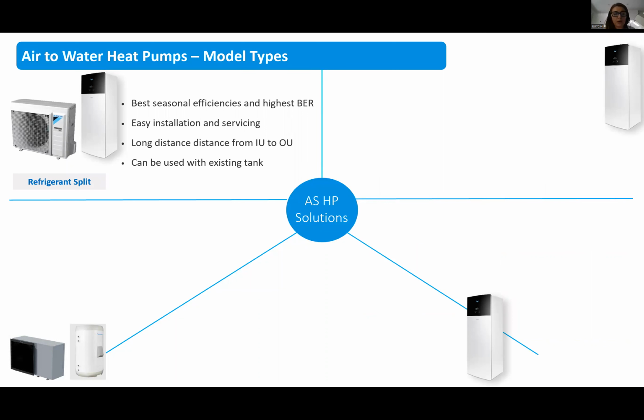So the first one here on the top right is a refrigerant split, and that means you have a refrigerant connection going between the indoor and the outdoor unit. In order to install a refrigerant split, you need an F-gas qualified engineer on site to make the connections between the indoor and the outdoor unit. And these units generally come pre-charged for about 10 meters, but you can go up to a distance of 30 meters between the indoor and the outdoor unit. So when additional gas has to be added to the system, that's also a job for the F-gas engineer.